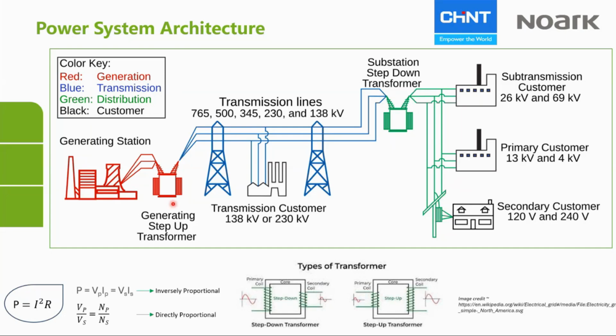Now, the reason why we go through a step-up transformer in this case is because there is an inverse relationship between current and voltage. So when the voltage goes up, the current comes down. That's how the step-up transformer works. Sorry, you have the voltage on the primary side very low and the current is more. Then when you step it up, you're increasing the voltage, and then the current is coming down.